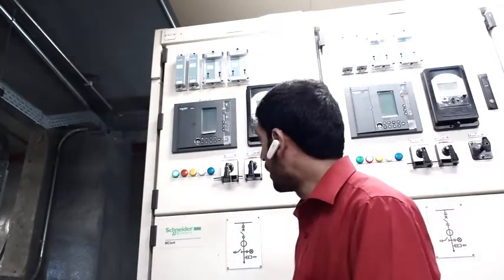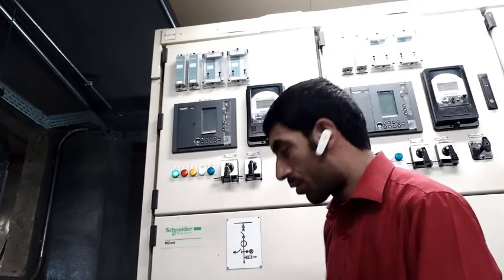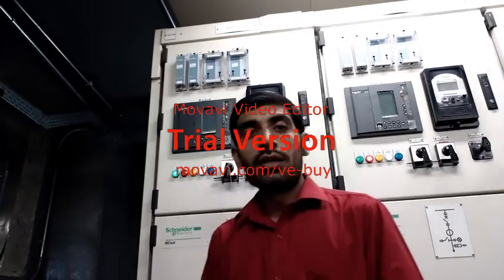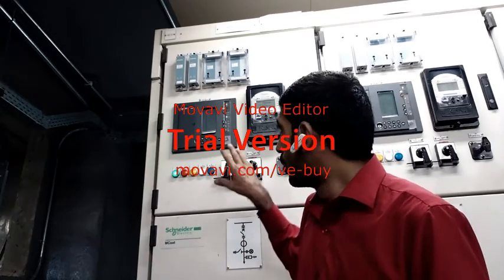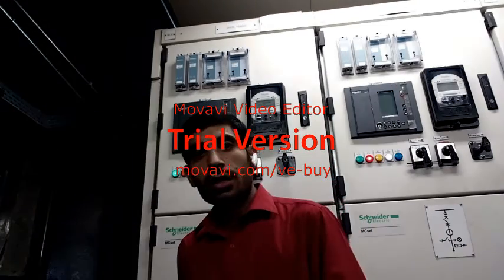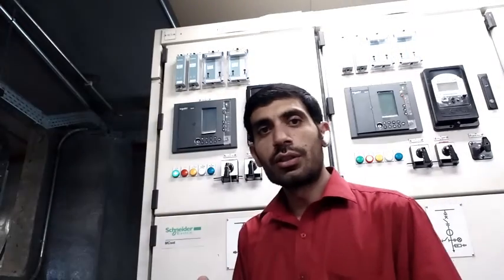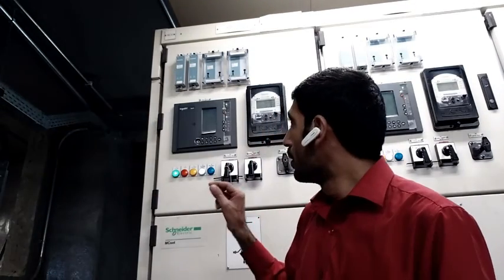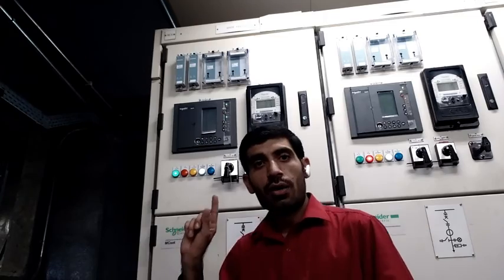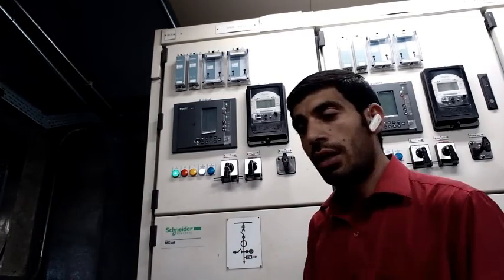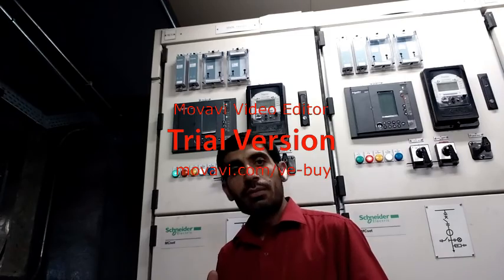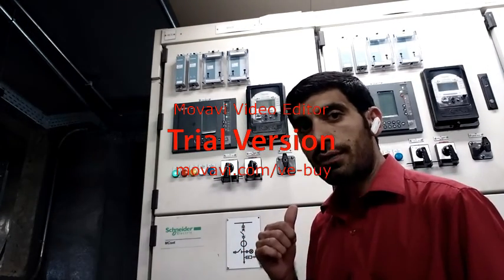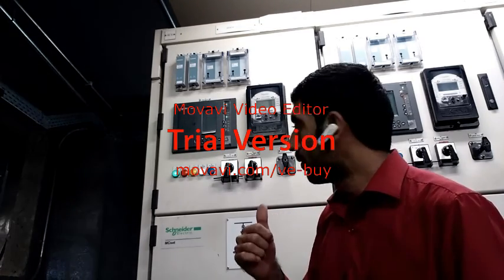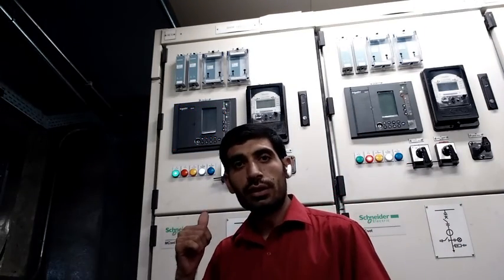So how does this relay work? If there is any problem on my side and my motor load increases, the rated load is 15 amps. So when the motor load increases up to 15, this will first give an overcurrent alarm, and then within the selected timing this relay will be tripped. For example, my selected time is 4 seconds. So within 4 seconds this relay will be tripped and give an overcurrent alarm.